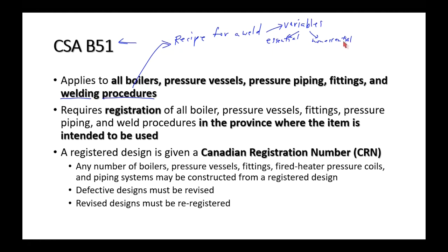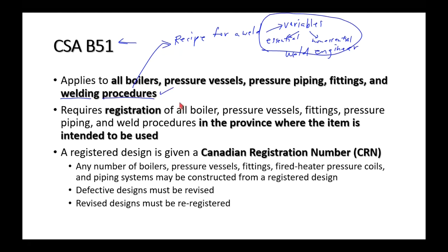For a weld, certain things are essential and certain things are non-essential. A weld engineer — a specialized mechanical engineer — designs a weld procedure. CSA says all weld procedures must be according to CSA B51. You can't just spray weld metal over pipes in your plant; there must be a weld procedure and a qualified welder conducting that procedure.